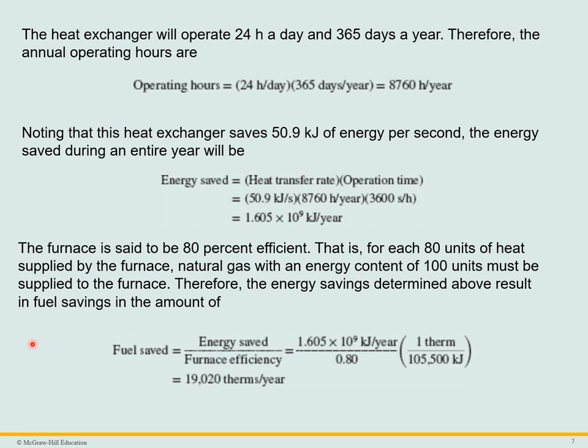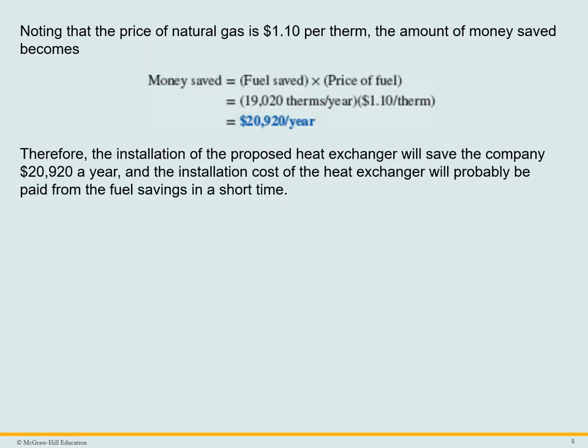Therefore, the fuel savings can be calculated as the energy saved divided by the furnace efficiency, which comes out to 19,020 therms per year. Noting that the price of natural gas is $1.10 per therm, the amount of money saved becomes $20,920 per year. Therefore, the installation of the proposed heat exchanger will save the company $20,920 a year.